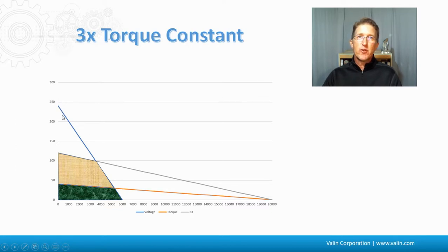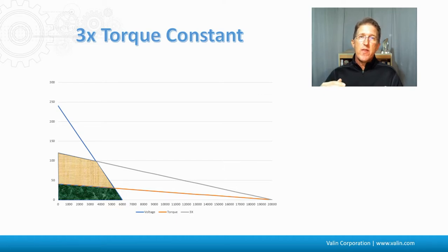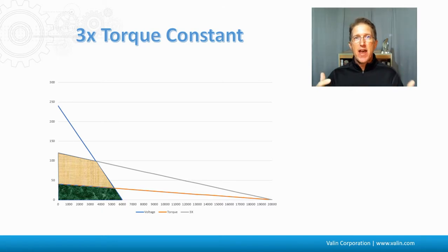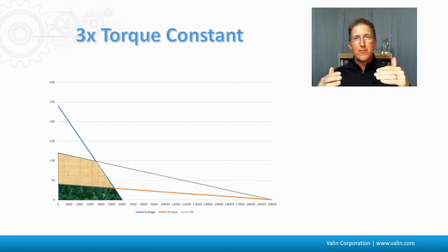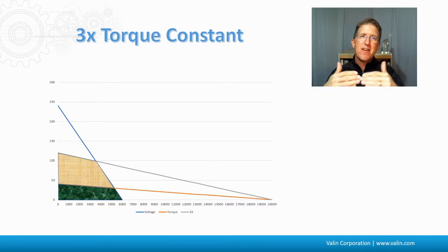The faster a motor goes, it turns into a generator. As the motor spins up, it creates back EMF — that's the voltage it produces. When that voltage meets the voltage going in, that's the maximum speed. The maximum voltage going in is the bus voltage of the drive. For example, 120 volts AC gets rectified to 170 volts DC. When the motor spins fast enough to generate 170 volts DC of back EMF, the motor can't go any faster because there's no more potential from the drive.